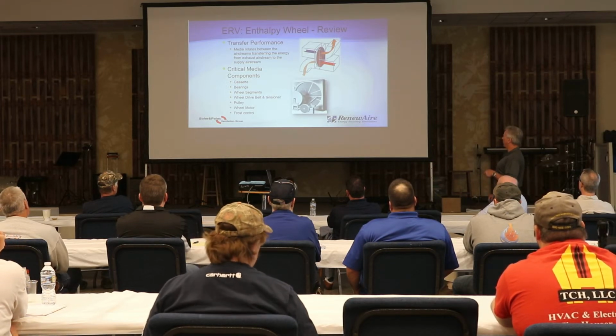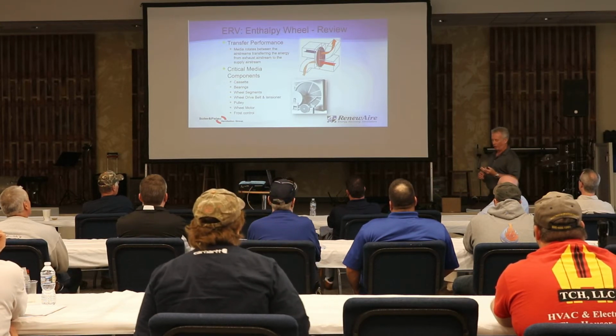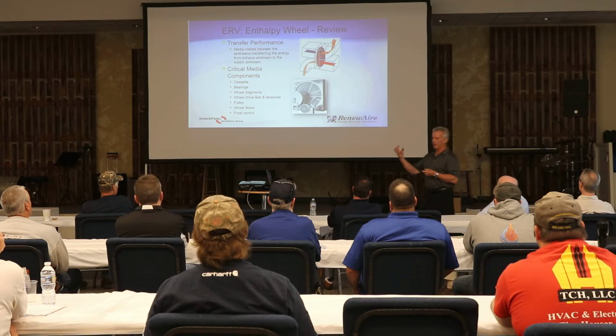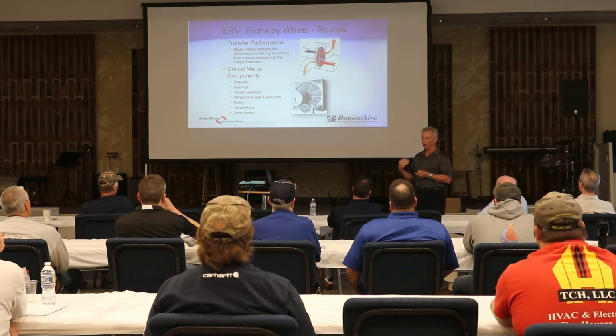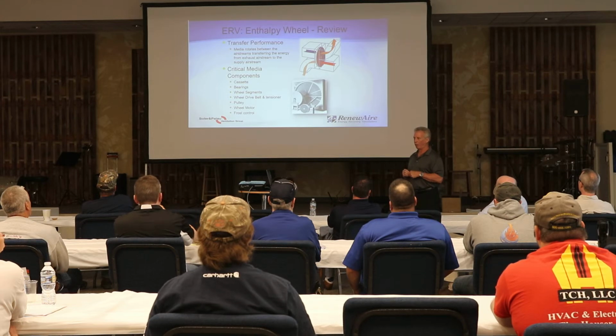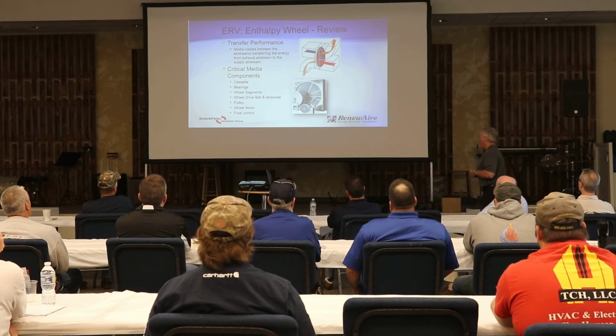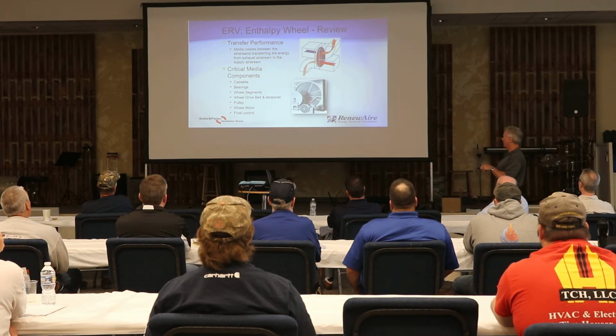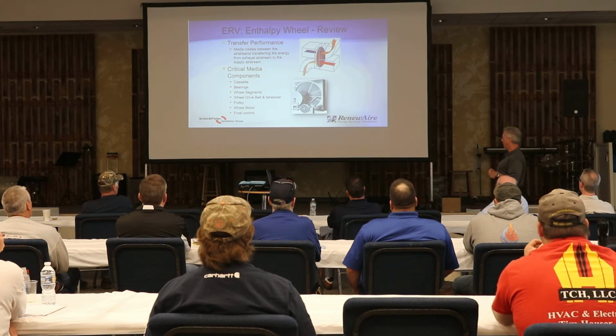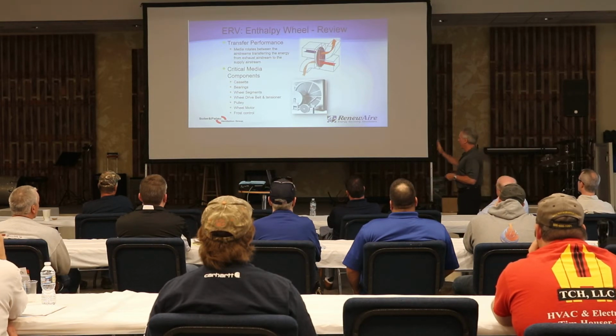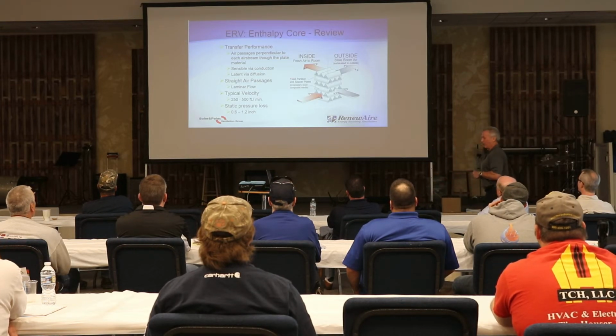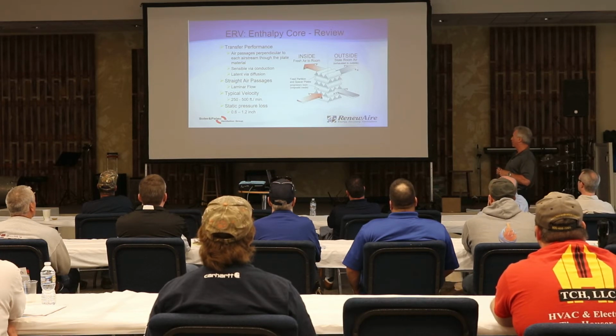The issues with enthalpy wheels: first of all, because of the nature of the desiccant, it does a very good latent exchange, as well as the sensible exchange. It will outperform a static plate enthalpy core on the latent exchange. But you're giving up a lot for that. You've got a lot of moving parts here, and the maintenance on it is much higher. You also run the risk of building up frost in that core. So that's the quick version of enthalpy wheels.